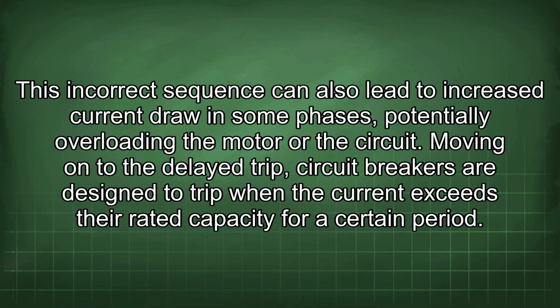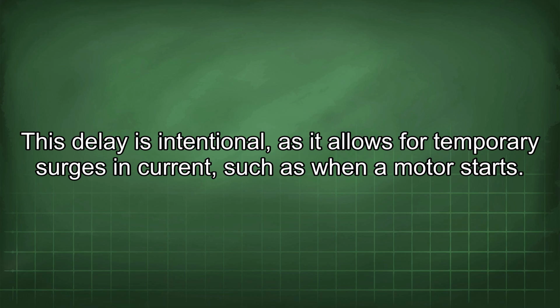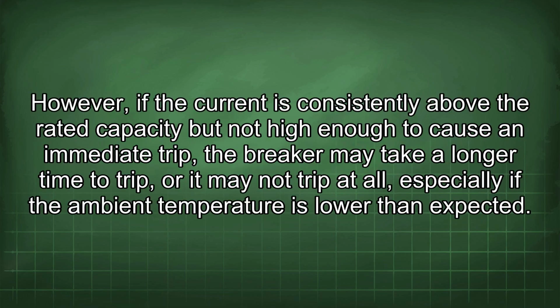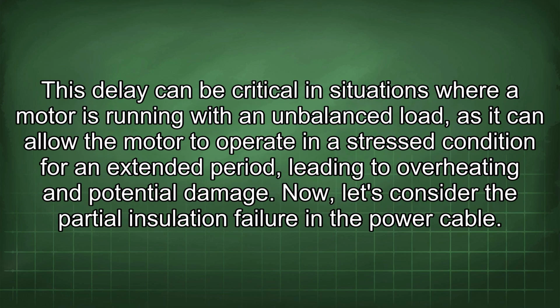Moving on to the delayed trip. Circuit breakers are designed to trip when the current exceeds their rated capacity for a certain period. This delay is intentional, as it allows for temporary surges in current, such as when a motor starts. However, if the current is consistently above the rated capacity, but not high enough to cause an immediate trip, the breaker may take a longer time to trip, or it may not trip at all, especially if the ambient temperature is lower than expected. This delay can be critical in situations where a motor is running with an unbalanced load, as it can allow the motor to operate in a stress condition for an extended period, leading to overheating and potential damage.